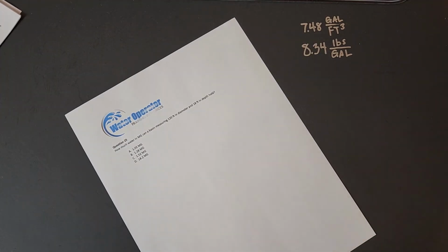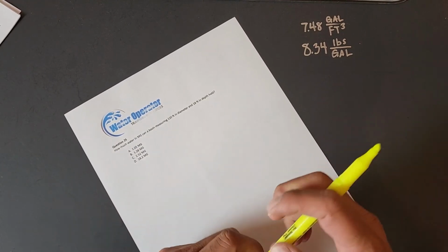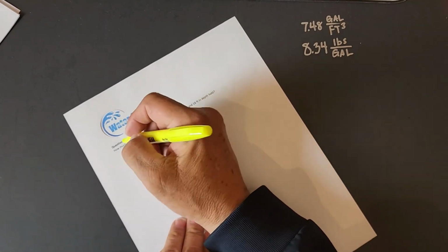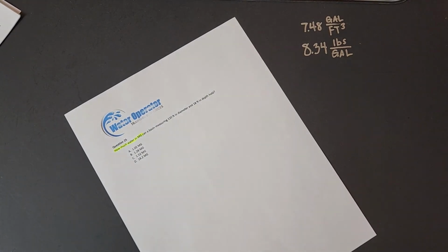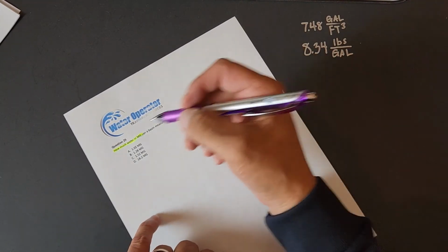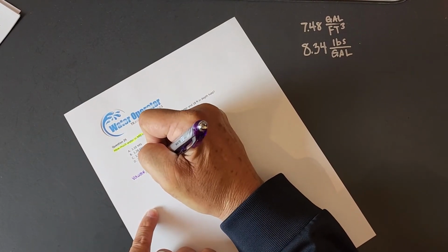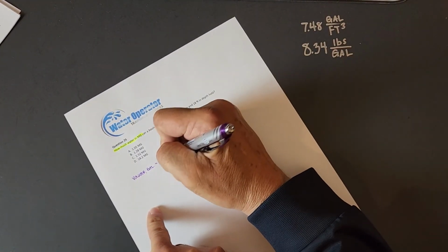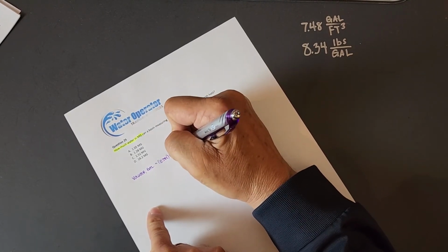Question 25. How much water in MG, million gallons, can a basin measuring 120 feet in diameter and 18 feet in depth hold? So we have how much water in MG, million gallons.